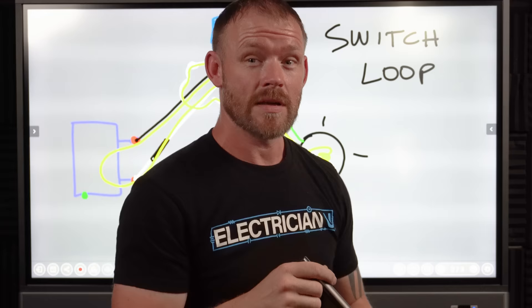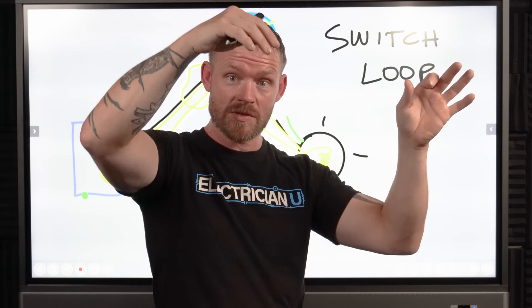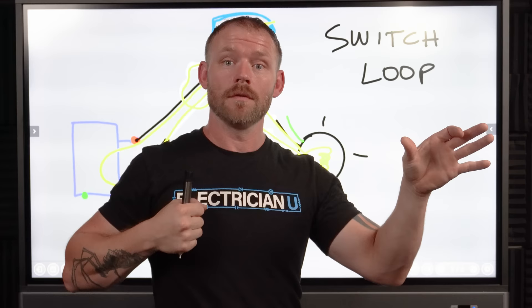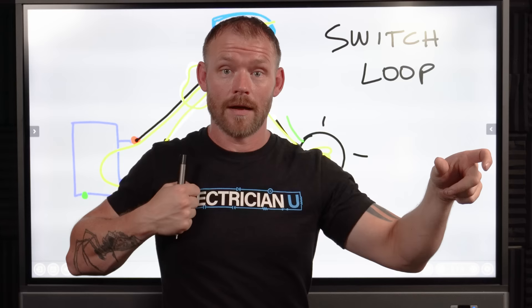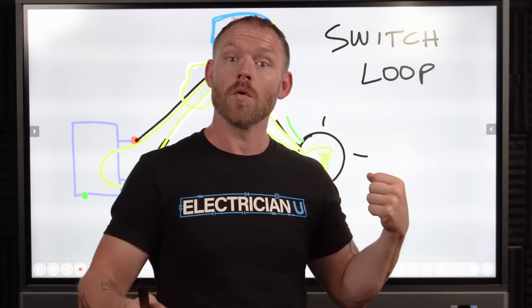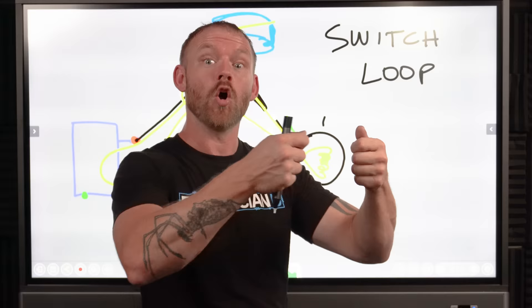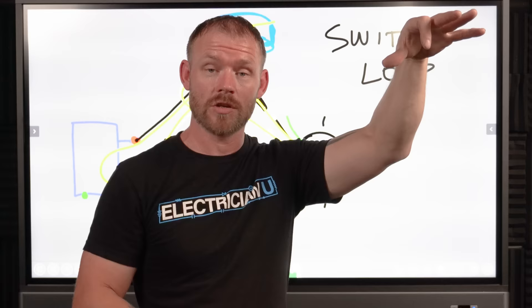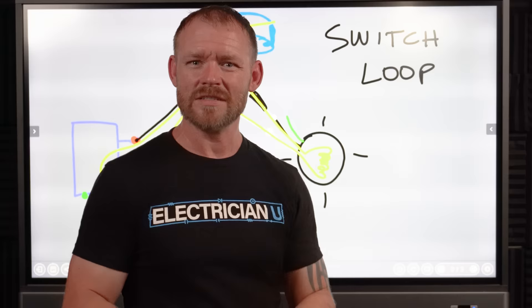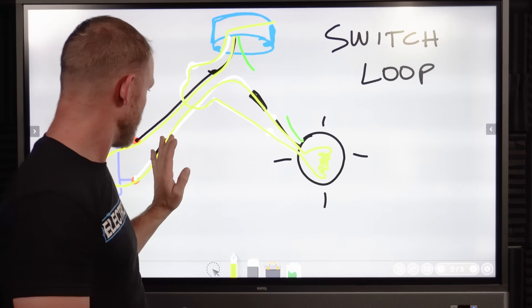That is a switch loop — you've got a hot up in the light box and you run two conductors down to send a hot down and a leg back up. A lot of door jam switches run off the same phenomenon: we run a hot up into a closet, put a door jam switch in so when you open the door the switch closes internally, turns the light on, and when you shut the door it depresses the button, opens the circuit, and shuts the light off. We do this a lot in closets, pantries, and cabinets where people want to open a door and have LED strips come on. The hot runs to the light location and two conductors run down to the door jam switch.